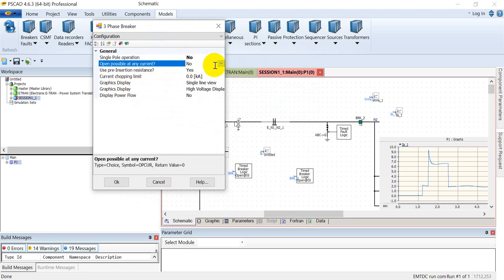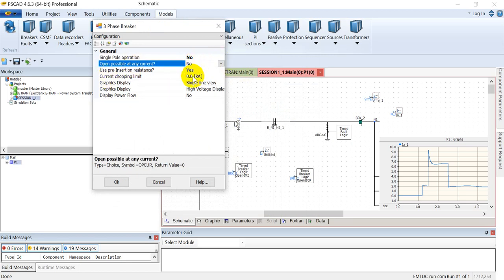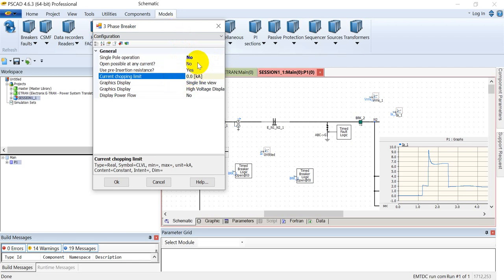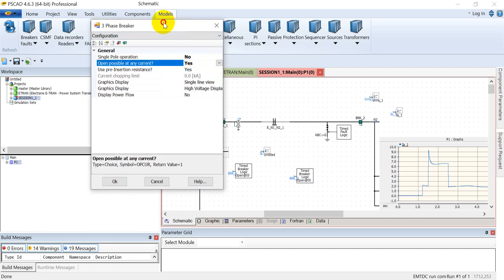The next one is open possible at any current. If we select it as no, then we can set the current chopping limit here. For example, if it is set at zero, then whenever an open signal is sent to the circuit breaker, it will open at the next zero crossing.